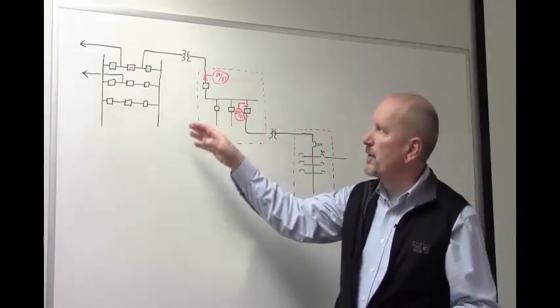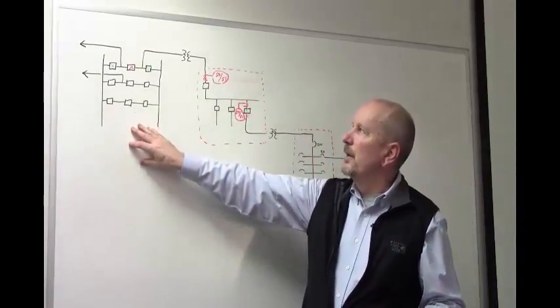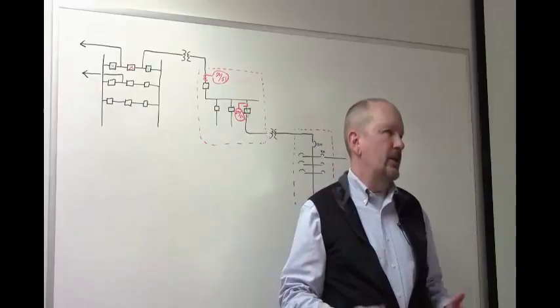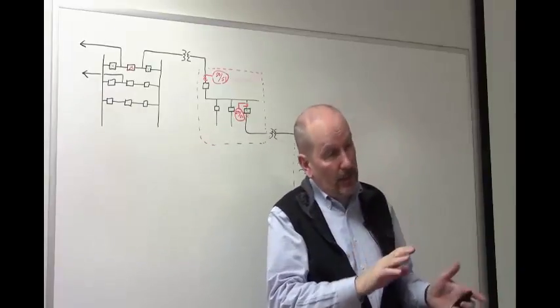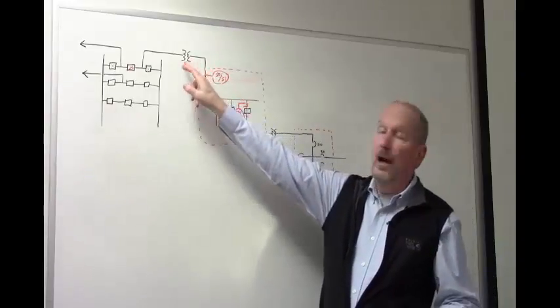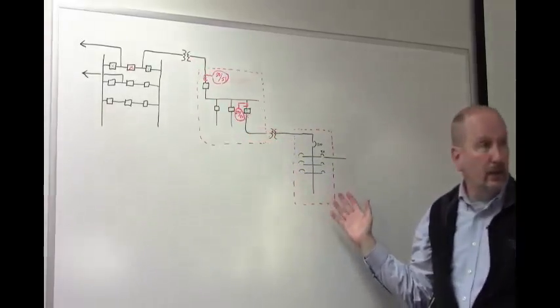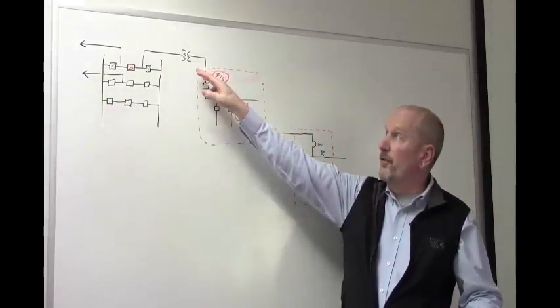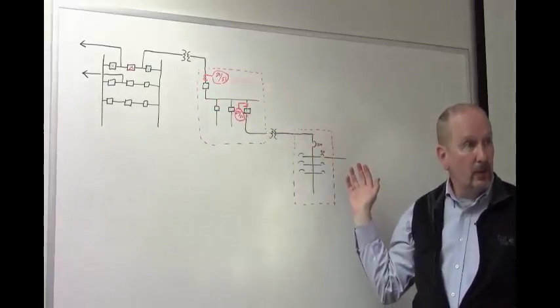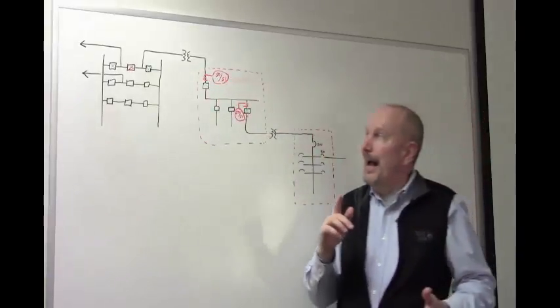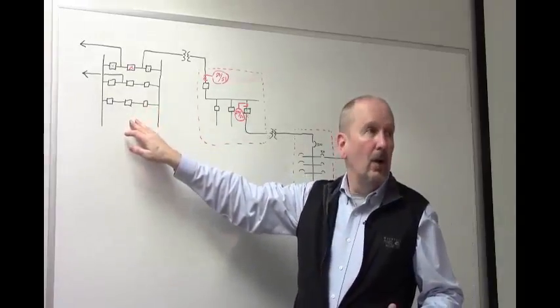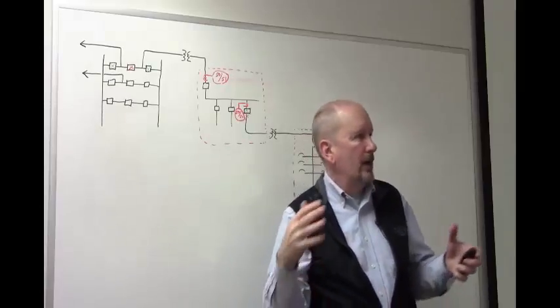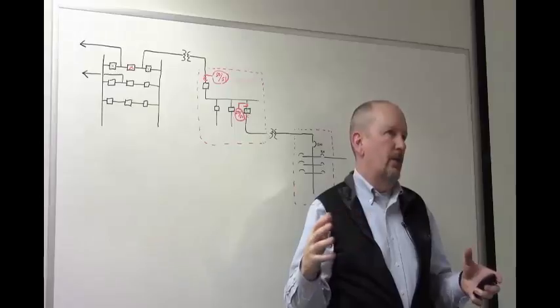Now let's take another step up in voltage to the transmission system. It gets a lot more complicated because it's no longer a radial system. In a radial system you just have a source upstream and none downstream, so you can safely assume all fault current flows in one direction. But at transmission level, you no longer have that assumption.